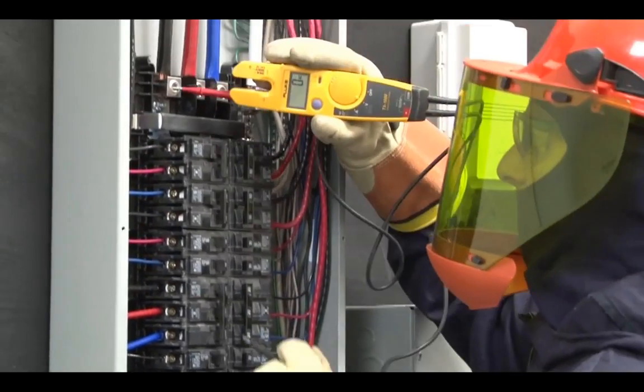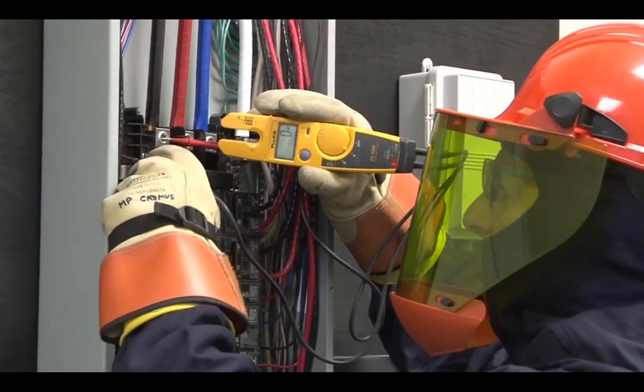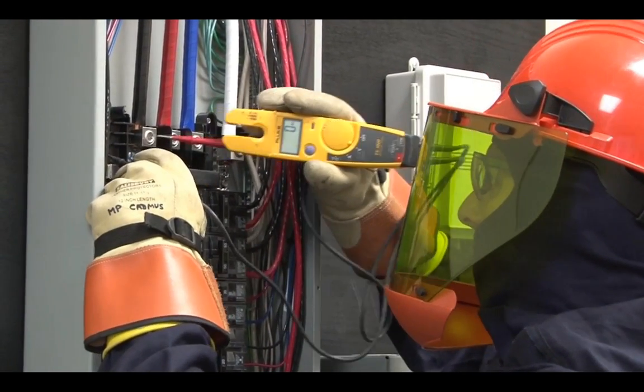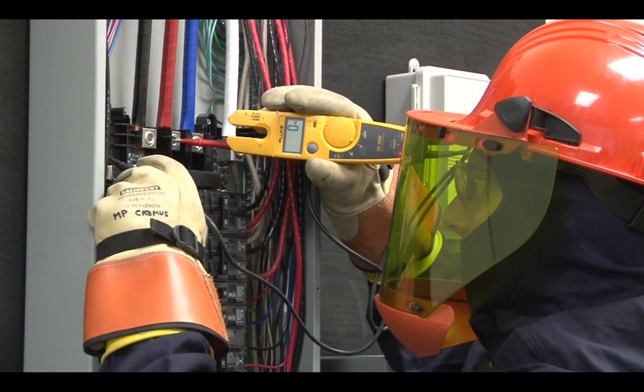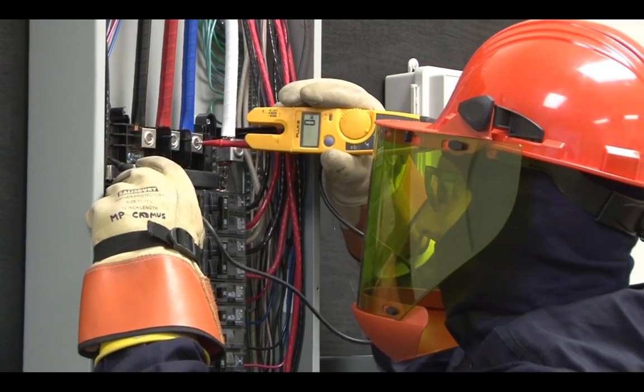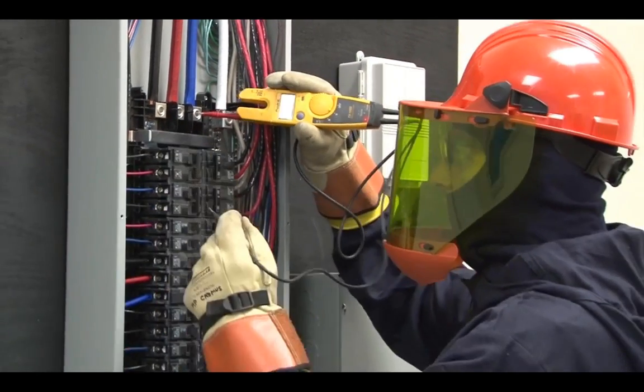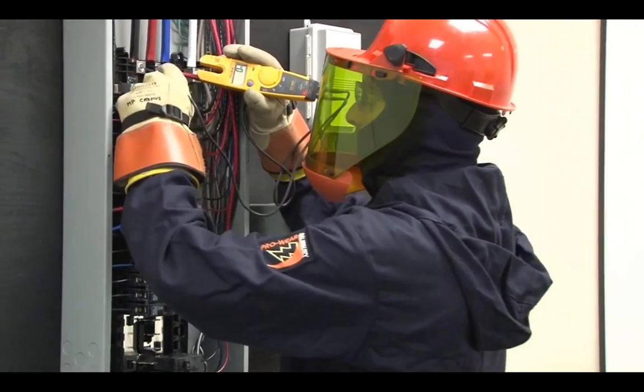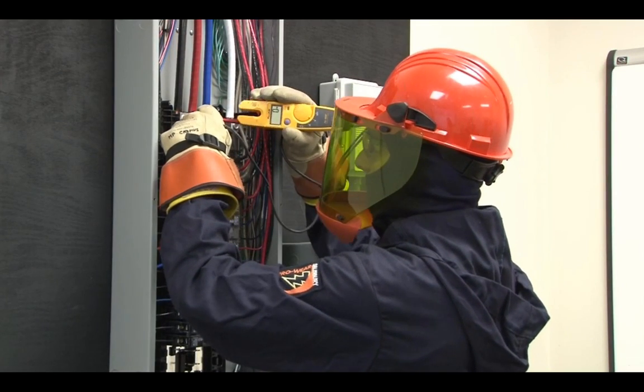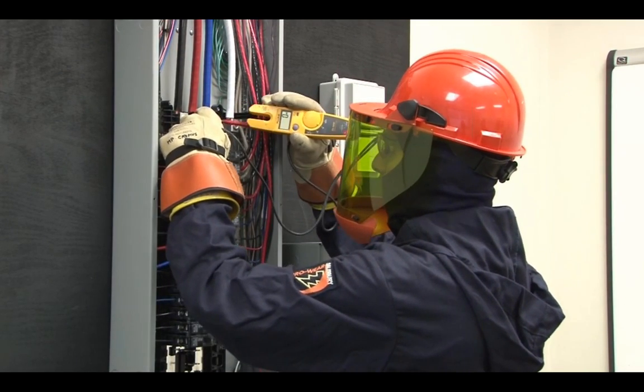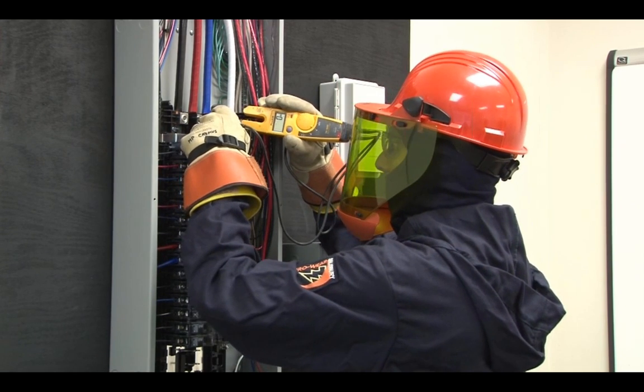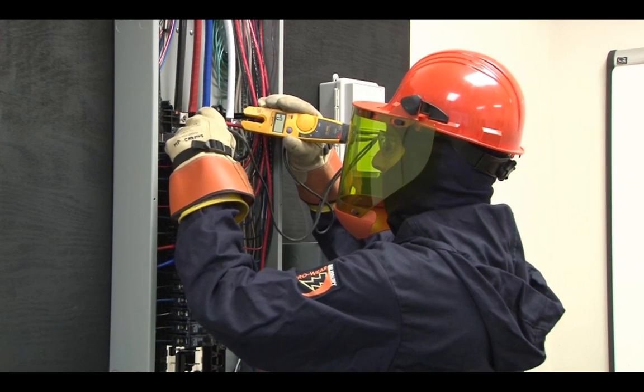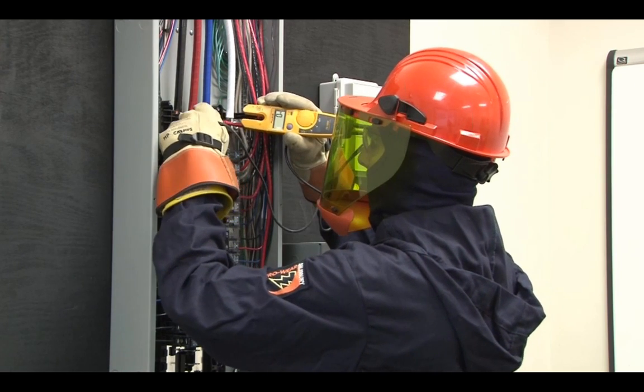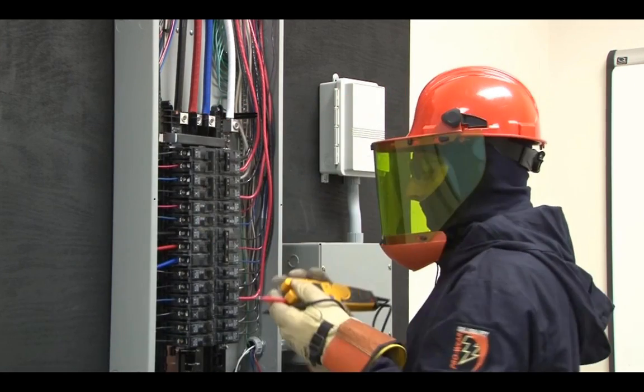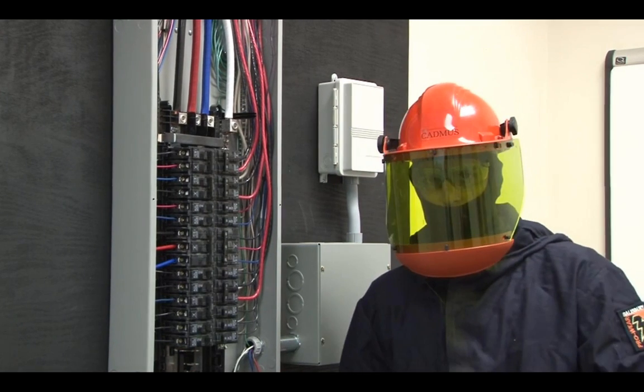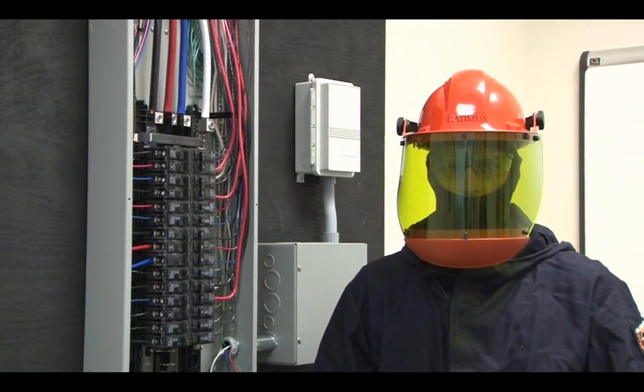We'll start with phase A to the neutral conductor. We should read approximately 120 volts. We'll then move on to phase B and phase C and get the same reading. We'll then check the voltage phase to phase, measure the voltage between phase A and phase B, and phase B and phase C, and phase A and phase C. For this, we should read approximately 208 volts. Once we've confirmed our voltage, we can now install our data logging equipment in the panel.